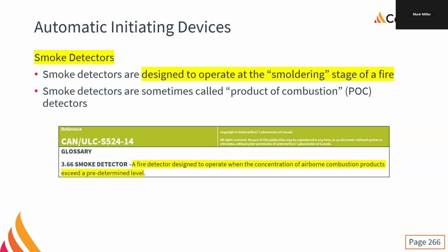So from S524, a smoke detector is a fire detector, because it still falls under the umbrella of a fire detector designed to operate when the concentration of airborne combustion products exceeds a predetermined level. And that predetermined level is decided at the factory. The adjustments, the sensitivities, are set at the factory, and then they put some schmoo on it, basically like a caulking compound, to make sure that no one can mess with them later.